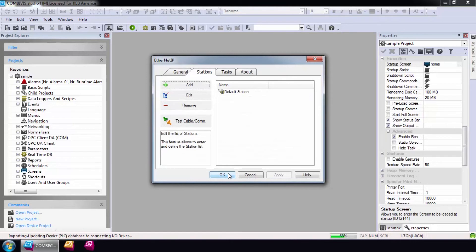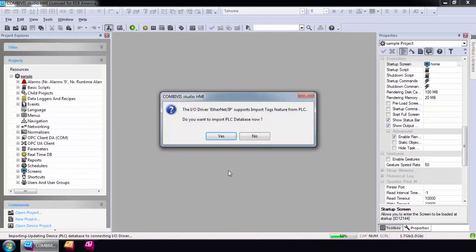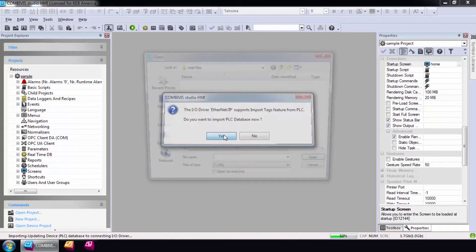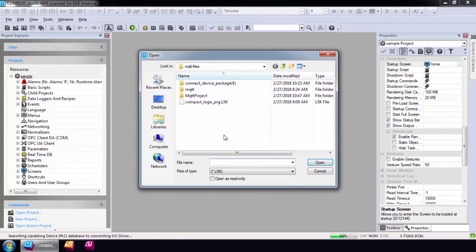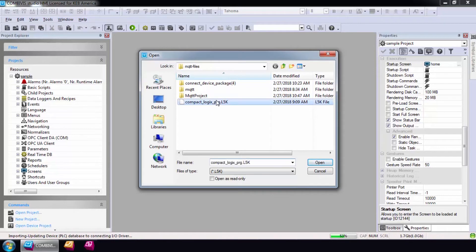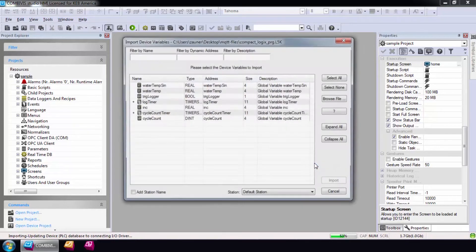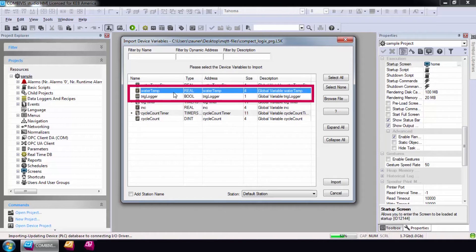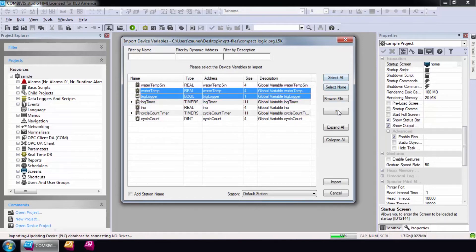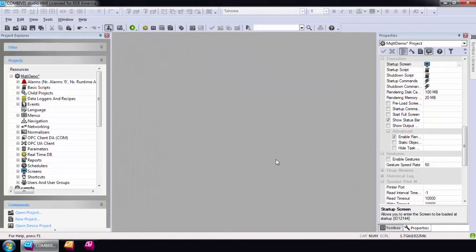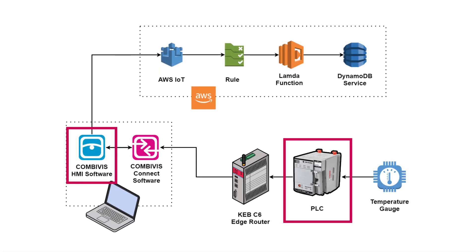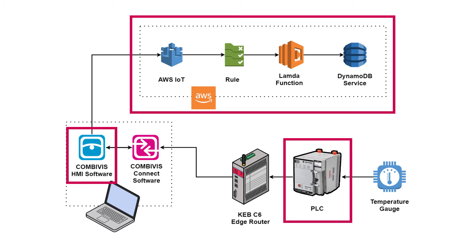And now I can add in tags from my PLC project. An option to import tags from a database will open. Rockwell Software allows projects to be saved as an L5K file or CSV file. I'll import my sample project from an L5K file. Once opened, all the tags in the project will populate. Only select the tags needed and select Import. Data communication between the PLC is now configured. The next step is to create a data logger within our project that will publish the tags collected from the CompactLogix to the AWS cloud.